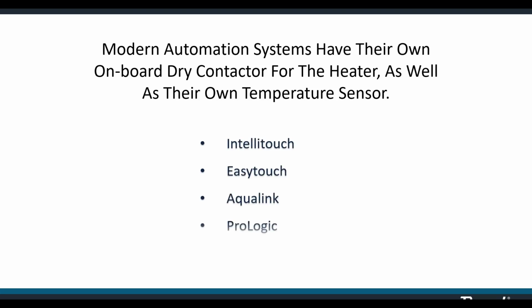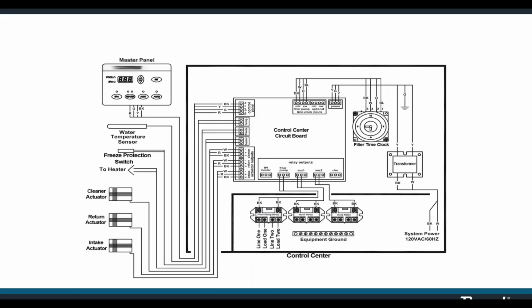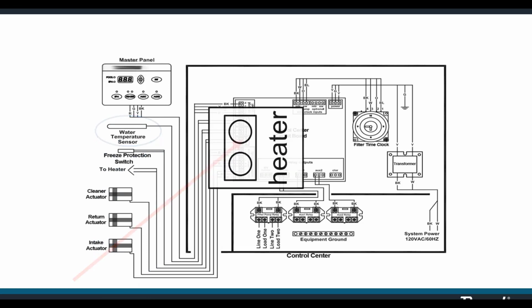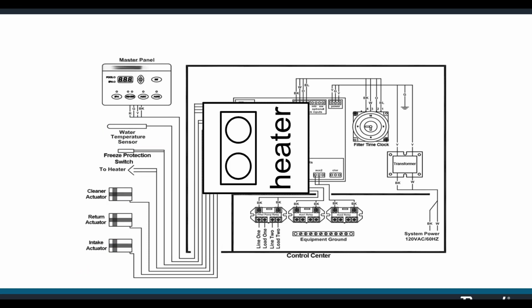They monitor the water temperature on their own, and when heat is necessary, they close a contactor, okay? That's all they do. That's all they know. Your automation system doesn't know what a swimming pool heater is, doesn't have a clue. All it knows how to do is close a contactor, and the heater takes it from there. So here's an example. Here's the temp sensor for the automation system. Here's the contactor up here, okay? So it amounts to putting one wire to one side of that contactor and one wire to the other side.